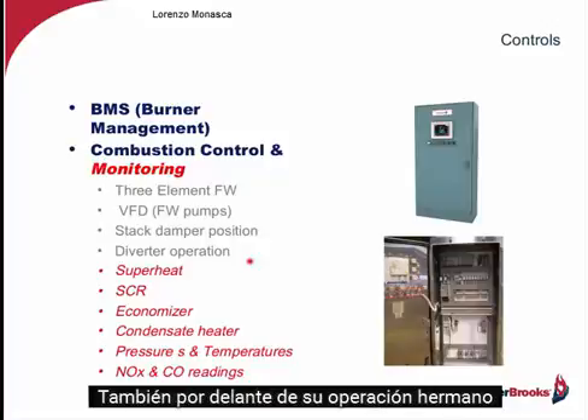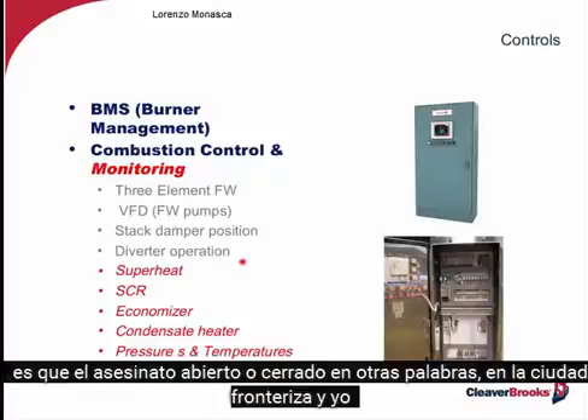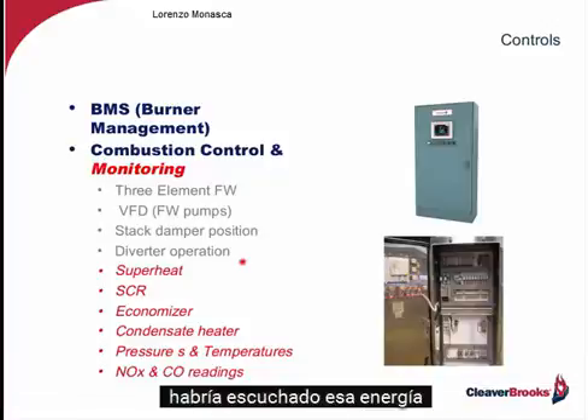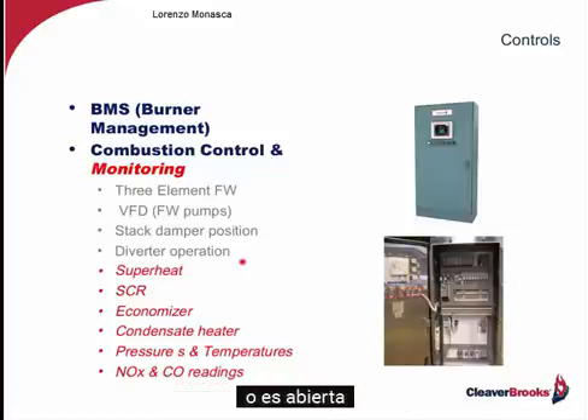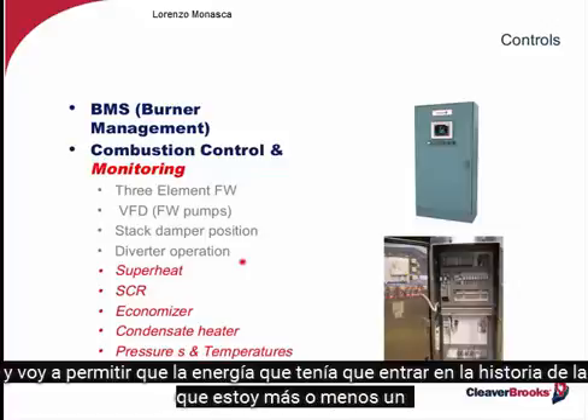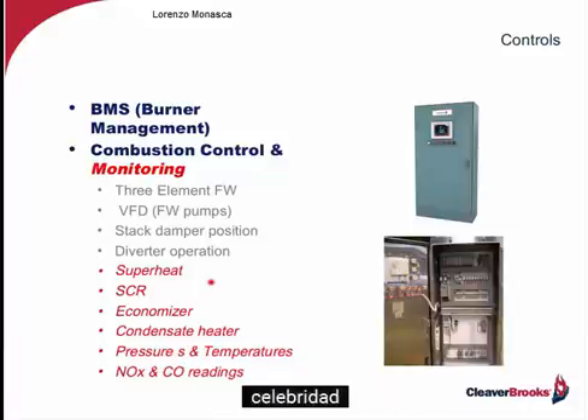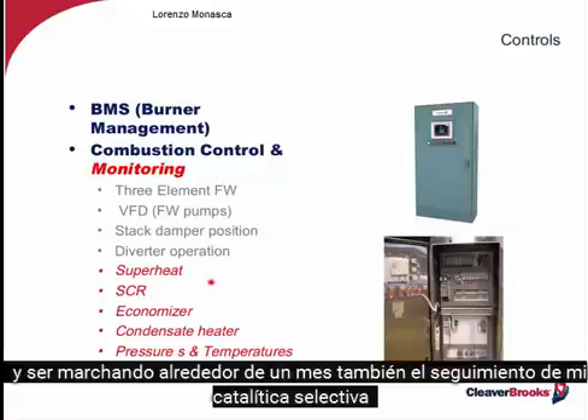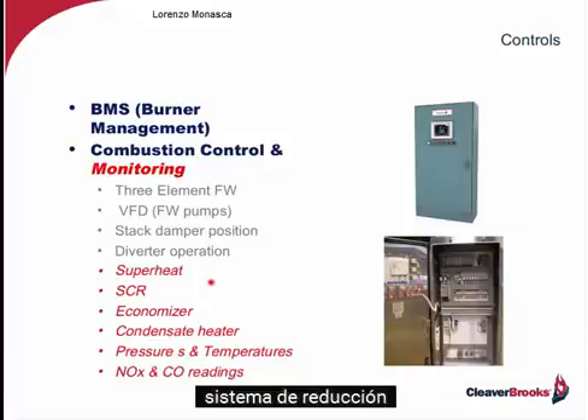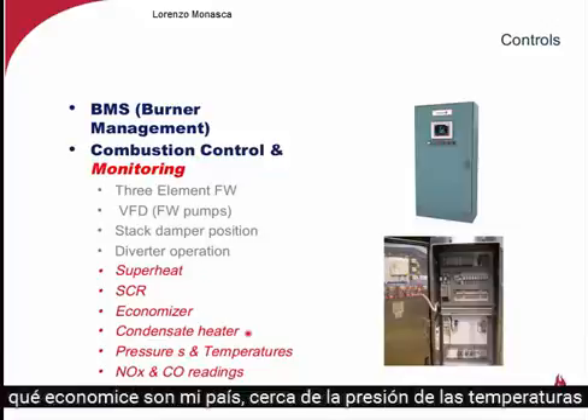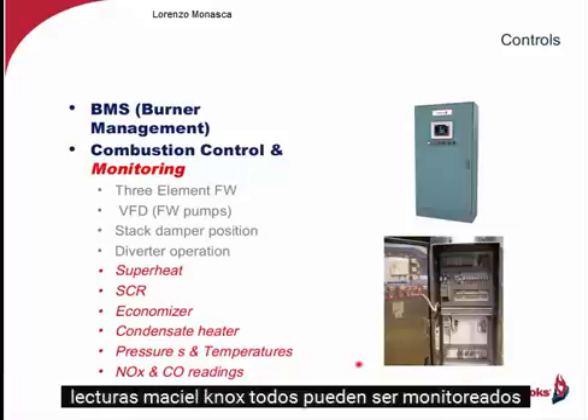I also have a diverter operation. This is all part of my combustion control. Is that diverter open or closed? In other words, is the boiler down and I'm going to divert that energy? Or is it open and I will allow that energy then to go into my HRSG? I'm going to be monitoring superheat. I'm going to be also monitoring my selective catalytic reduction system, my economizer, my condensate heater, the pressure and temperatures, all of these things. The NOx and the CO readings can all be monitored.